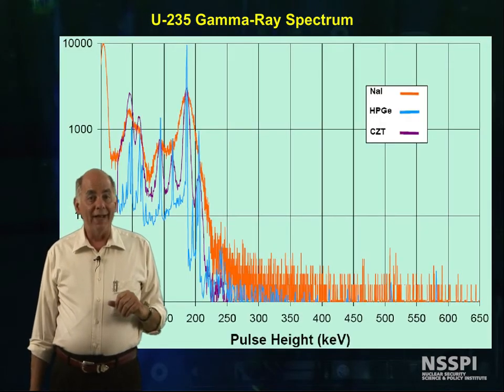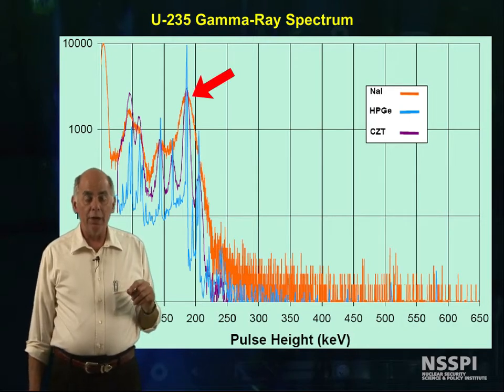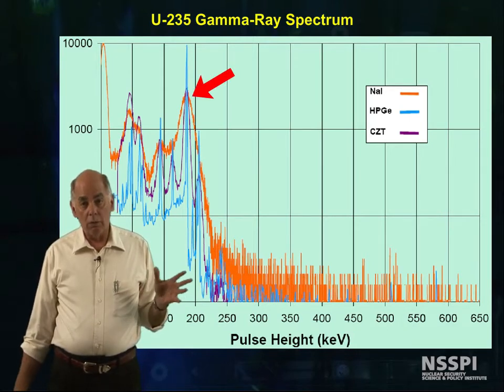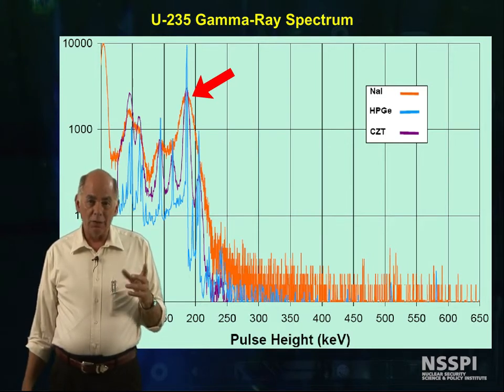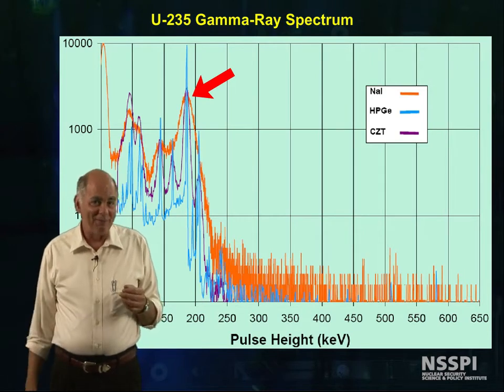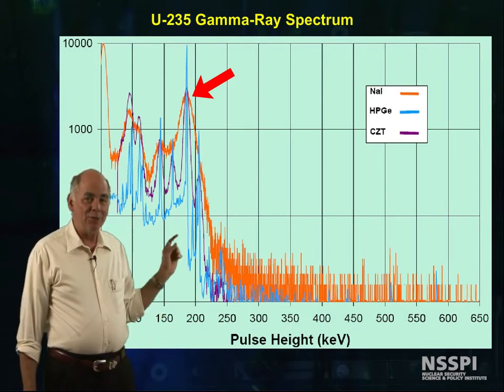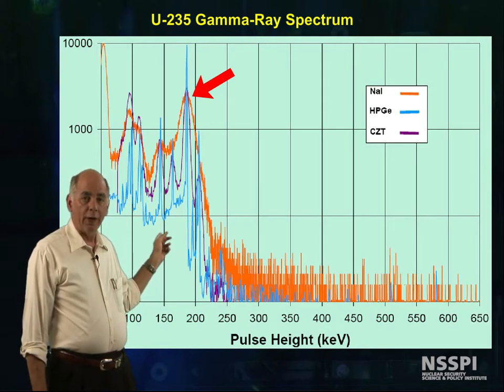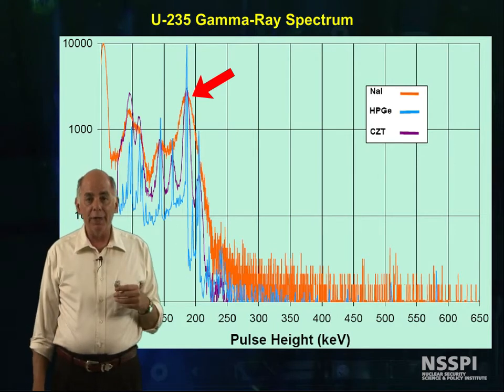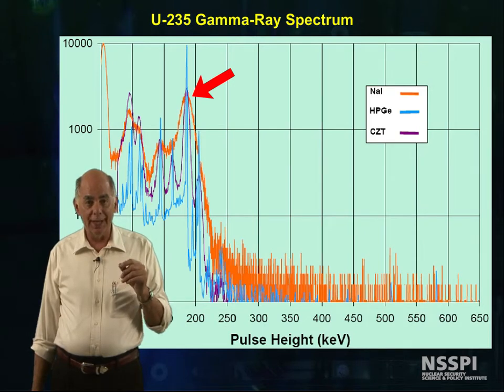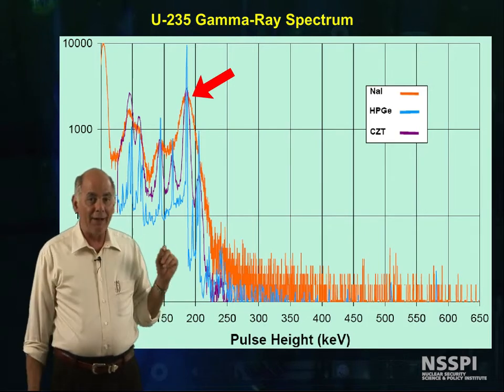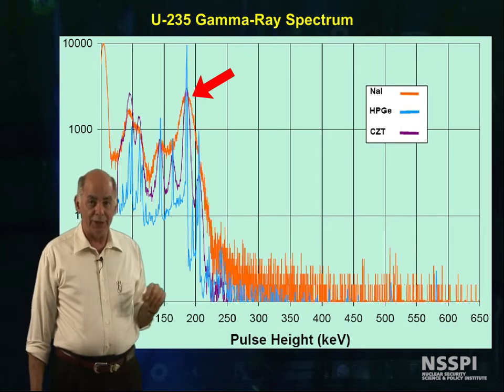If the sample were LEU, we would have a Compton continuum in that area from the 1001 keV peak from U-238, which is actually from the daughters. Since detectors are much more efficient for counting low-energy gammas than high-energy ones, it's very common to measure the enrichment of a sample by measuring the relative strength of the 186 keV peak to the Compton continuum above the 186 keV.